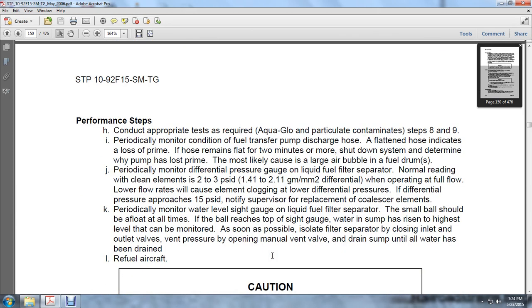Conduct appropriate tests as required for the presence of contaminants in steps 8 and 9. Periodically monitor the condition of the fuel transfer pump discharge hose. A flattened hose indicates the loss of prime. If the hose remains flat for 2 minutes or more, shut down the system and determine why the pump has lost prime. The most likely cause is large air bubbles in the fuel drum.